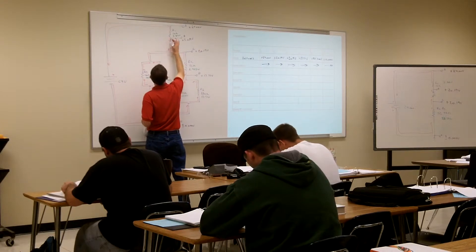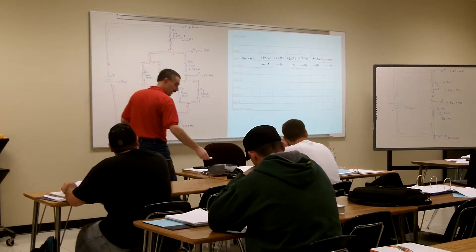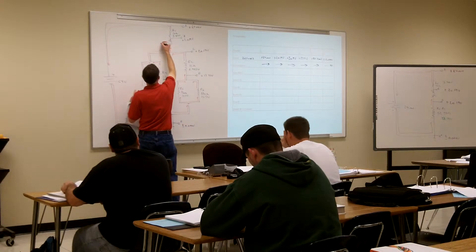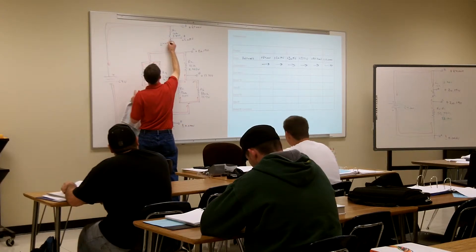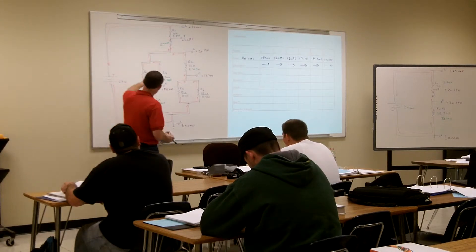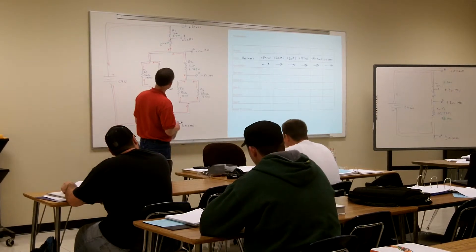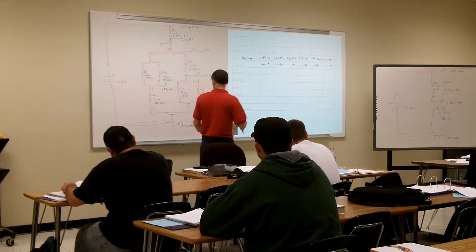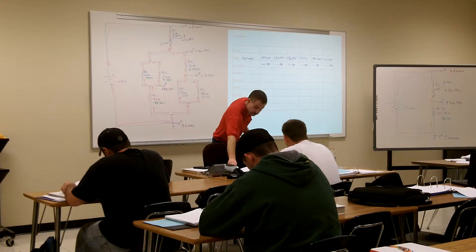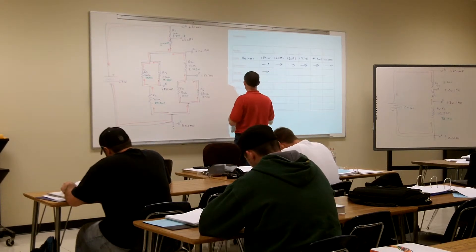Now I'm going to open up my switch. What's my voltage going to be across my switch? Source voltage — that's going to be my 24 volts. So what does that mean for all the other voltages? They're going to drop down to zero. So what's going to happen to test point A? It's going to stay the same — it's still going to be my source voltage because I'm measuring across the open or across the source.